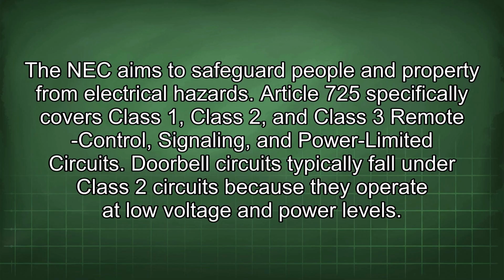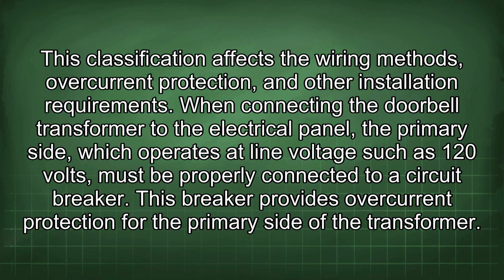Article 725 specifically covers Class 1, Class 2, and Class 3 remote control, signaling, and power-limited circuits. Doorbell circuits typically fall under Class 2 circuits because they operate at low voltage and power levels. This classification affects the wiring methods, overcurrent protection, and other installation requirements.